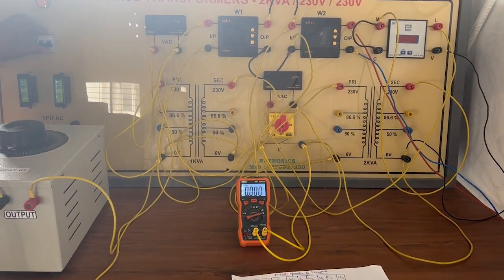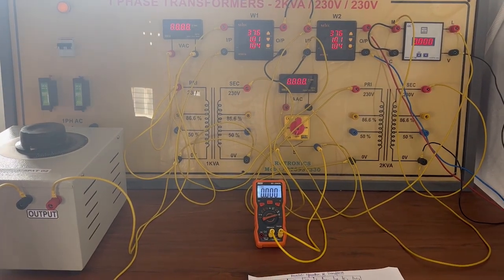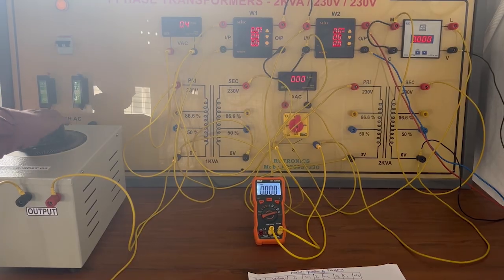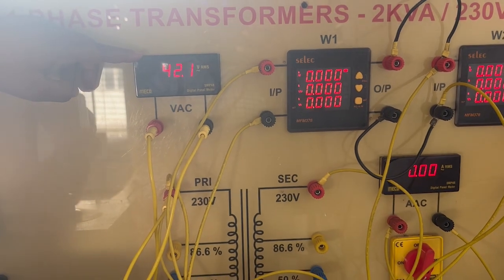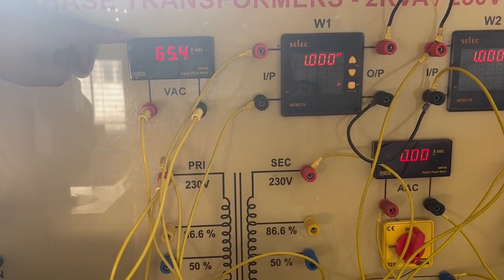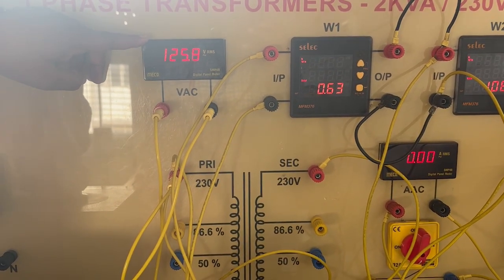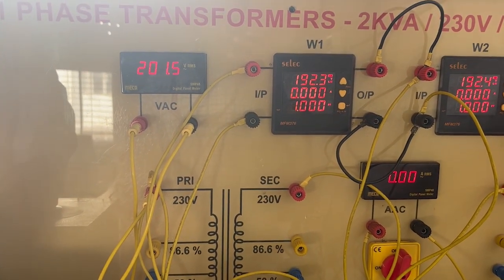So today we are going to study the experiment on parallel operation of two dissimilar transformers of different kVA ratings. After making the connections, we have to close the switch, right? Once you close the switch, you have to vary the single phase auto transformer to the rated voltage. This is the voltage. We are going to vary the voltage from the single phase auto transformer to the rated value of the single phase transformers. You can see now it is 230 volts.